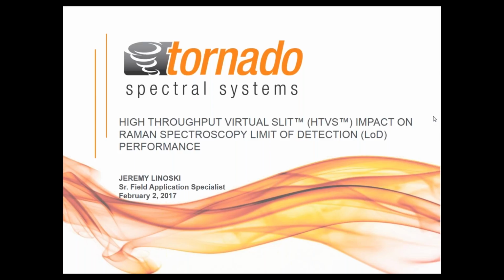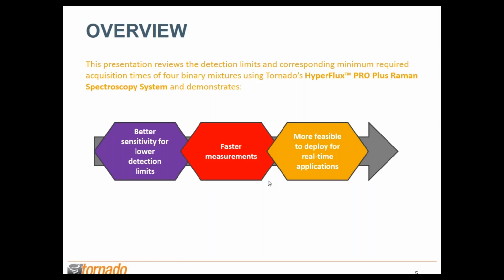This presentation reviews the detection limits and corresponding minimum required acquisition times of four tested binary mixtures using Tornado's HyperFlux Pro Plus Raman spectroscopy system. And it will demonstrate its better sensitivity for lower detection limits, doing so at faster measurement times, which in turn makes it more feasible to deploy for real-time process monitoring applications.